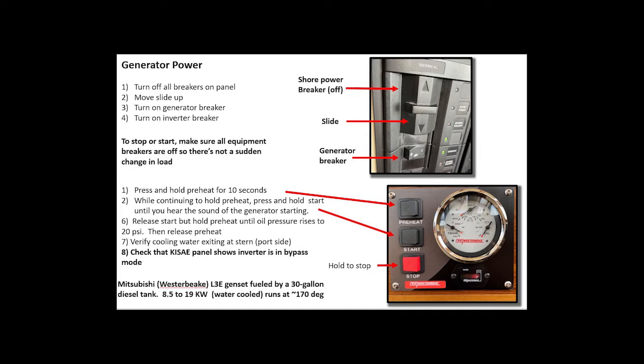Okay, so to start the generator, we press and hold preheat for 10 seconds, and then while we're continuing to hold that, I'll hold the start button till we hear the sound of the generator starting up, and we watch the oil pressure rise, and then we can release the start and hold the preheat until the oil pressure gets up to at least 20 psi, and then we can release the preheat.